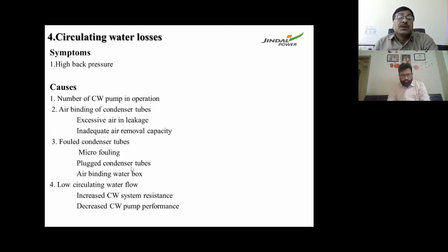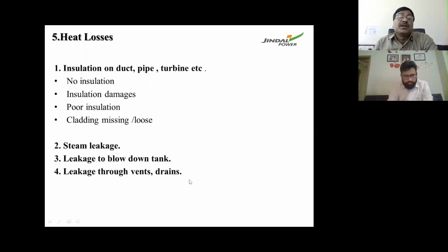Other losses are insulation on ducts, pipes and turbine, which should be regularly monitored. Sometimes there is no insulation somewhere where it is required, and due to heat radiation there is a loss. Sometimes the insulation gets damaged, or there is poor insulation. So an insulation survey is very important. A steam leakage survey is also important. It results in a lot of heat rate loss. Leakage to the blowdown tank, leakage through vents and drains, all leakages should be attended to as soon as we observe them.